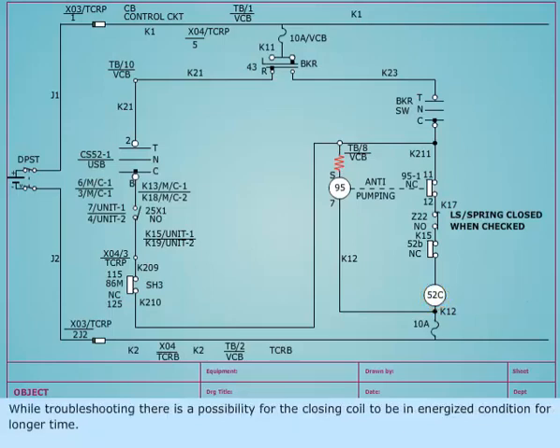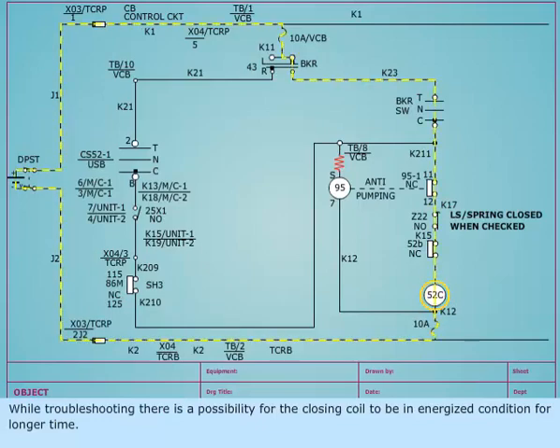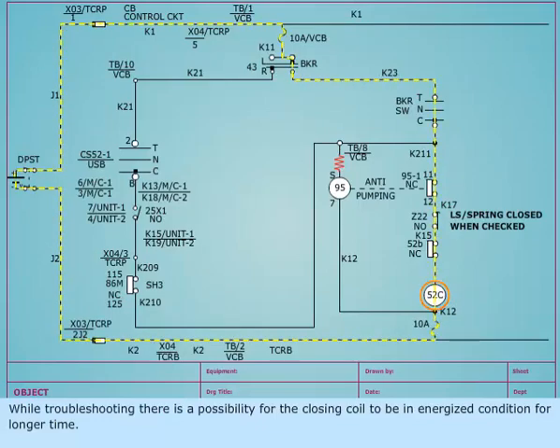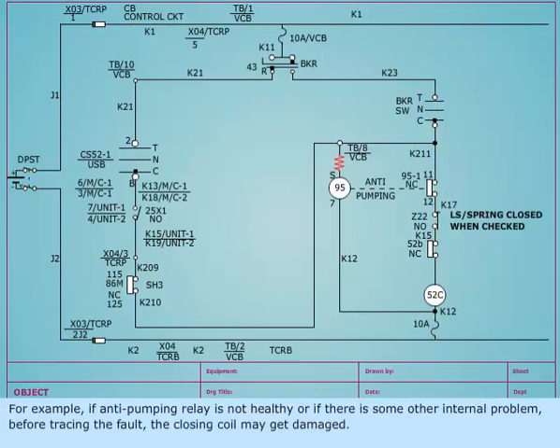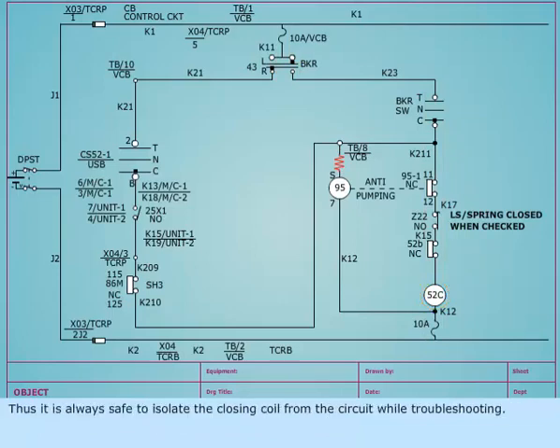While troubleshooting, there is a possibility for the closing coil to be in energized condition for a longer time. For example, if anti-pumping relay is not healthy or if there is some other internal problem before tracing the fault, the closing coil may get damaged. Thus, it is always safe to isolate the closing coil from the circuit while troubleshooting.